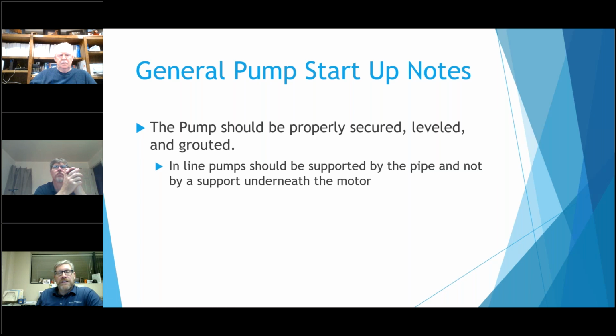I do understand why it's there, and I love to have it there. But what you want to do is make sure that you're able to freely swing that hanger underneath. So you don't want to actually support it, have it underneath, because these things are installed in the air, because that's where they've been asked to install them. Or even if they're close to the ground, it's great to have that third hand sitting there, but you just don't want it to actually support the pump. So you want to be able to swing the hanger beneath that motor, so you don't run into issues. I got a picture of where one was a little bit too tight, and the complaint was the pump was noisy. But yeah, you just want to make sure it's loose underneath it.